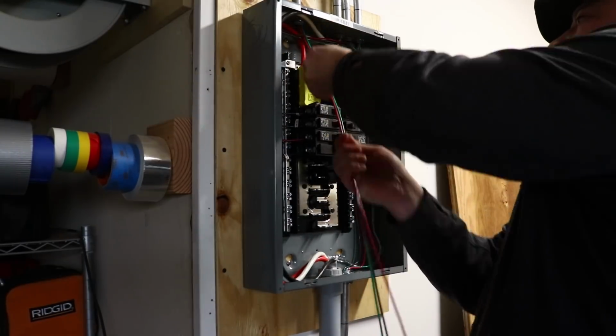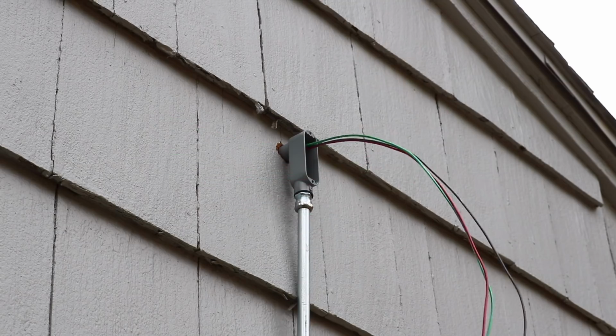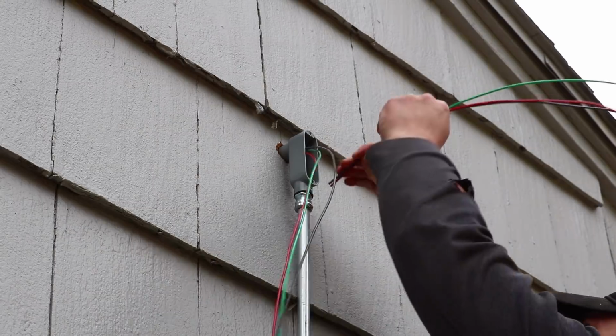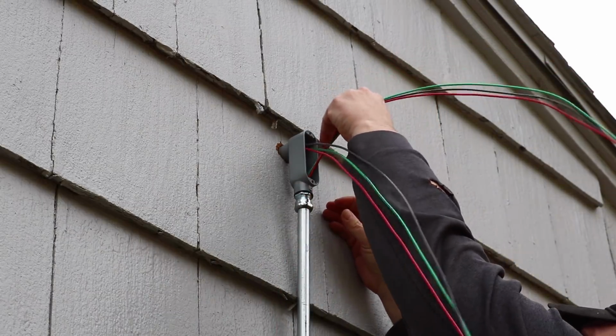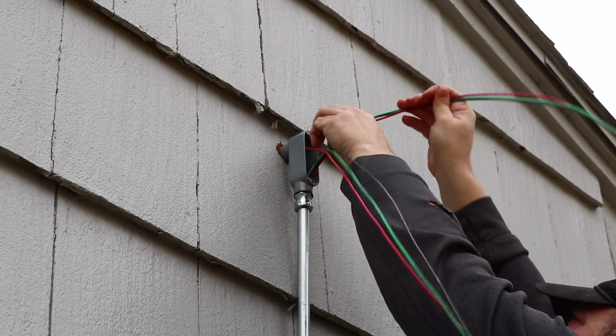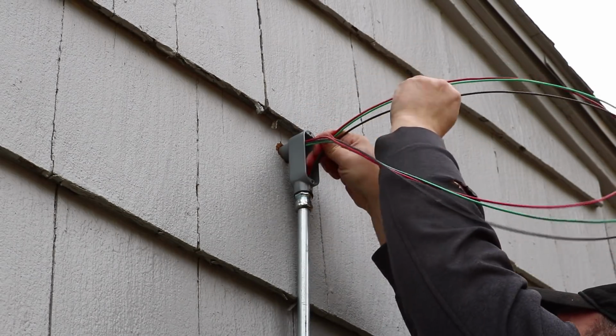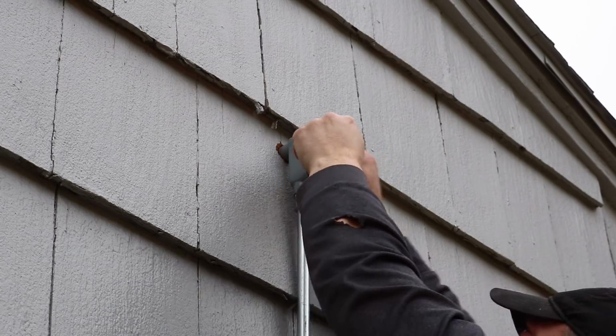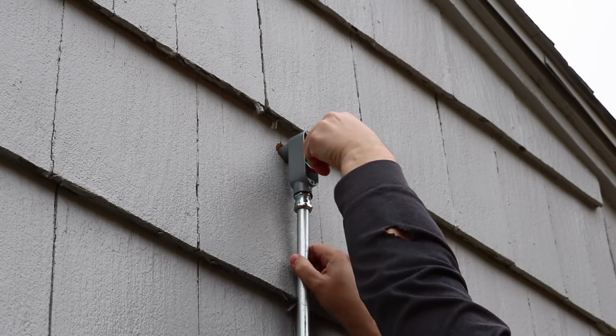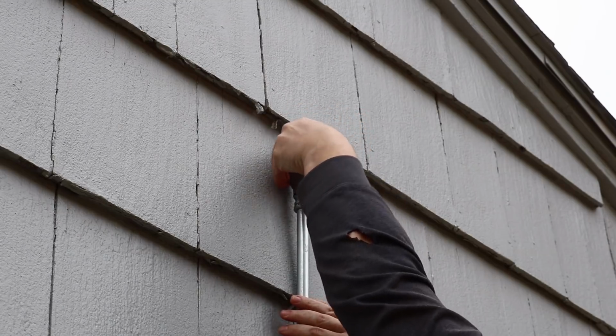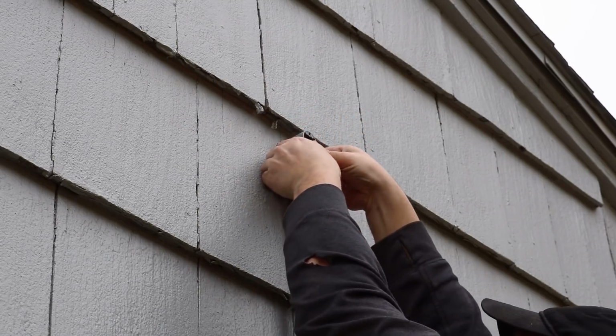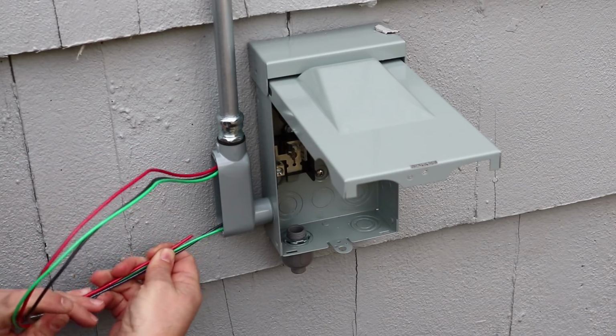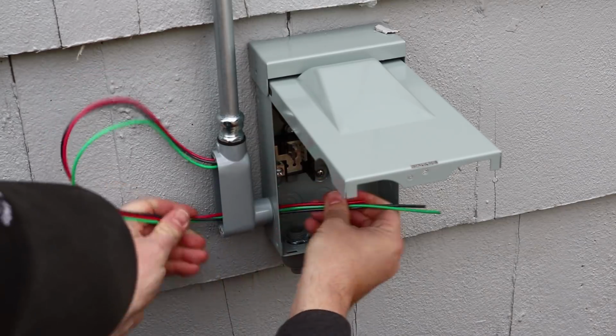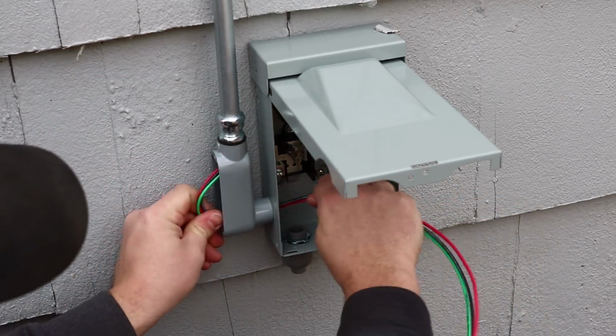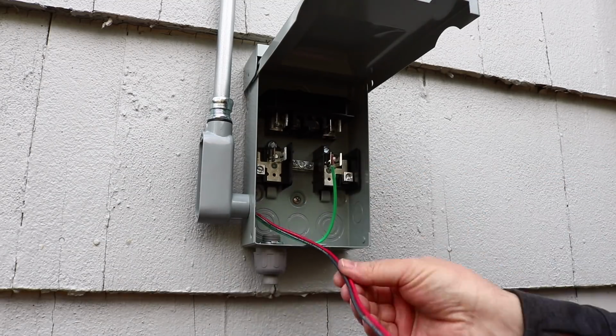With this being such a short run, I decided to just push the wires through by hand. A fish tape here would probably be more trouble than it's worth. Once I had the wires outside and through the L, I looped them around and sent them through the conduit down to the other L, where I will then send them into the disconnect box. This unit requires a 20 amp breaker, and that means I needed to use 12 gauge THHN. Actually, since it's going outdoors, it needs to be THWN, but what I've learned is that nowadays THHN and THWN are usually the same thing. I double checked the wire that I had on hand, and it in fact was THWN as well as THHN.